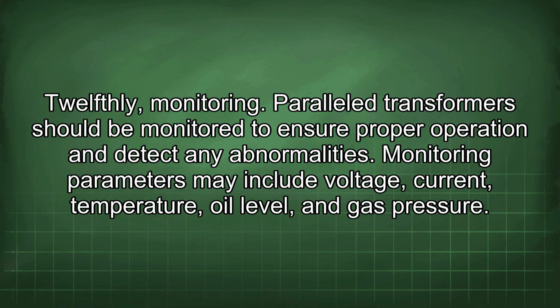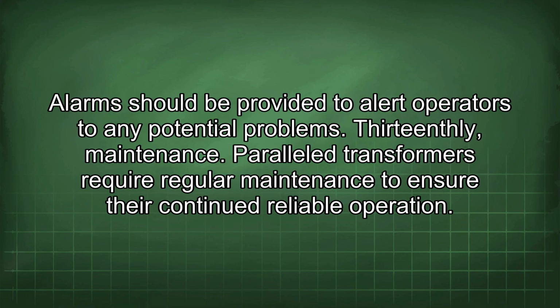Twelfthly, monitoring. Parallel transformers should be monitored to ensure proper operation and detect any abnormalities. Monitoring parameters may include voltage, current, temperature, oil level, and gas pressure. Alarms should be provided to alert operators to any potential problems.